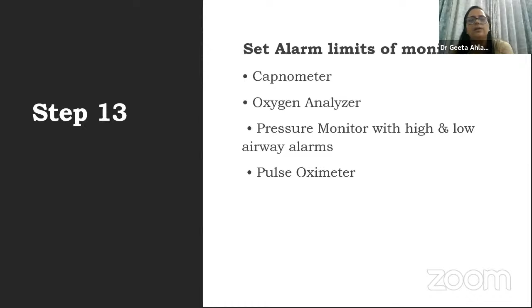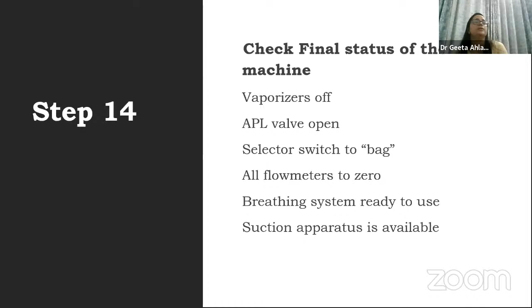Check final status of the machine. Vaporizer should be off. APL valve should be open. Again, I repeat, selector switch should be on the bag. All flow meters should be 0. Breathing circuit should be ready to use. Suction apparatus should be available to you. Having done all this, this should also be completed on paper. All documentation of complete checkout procedure should be done.